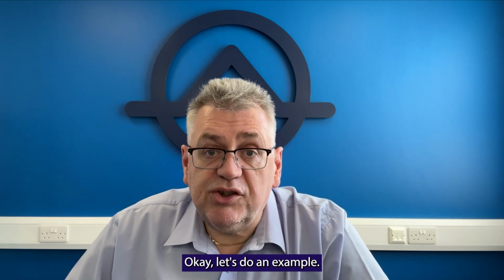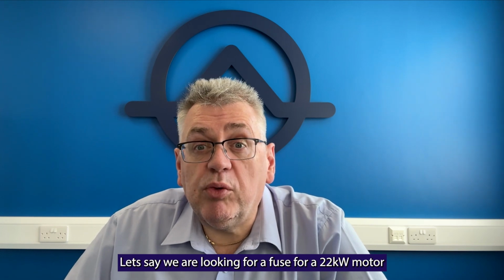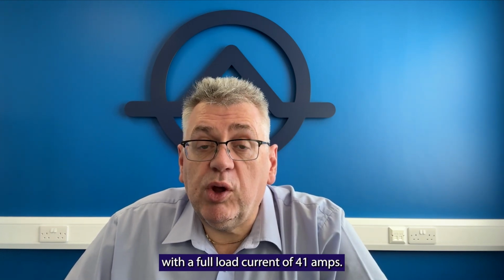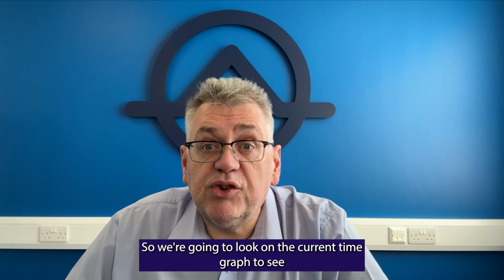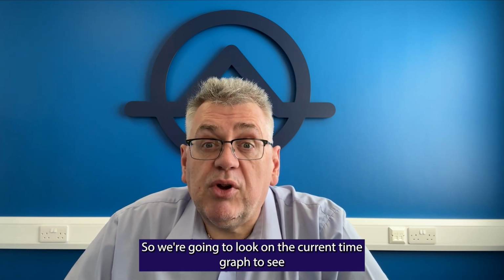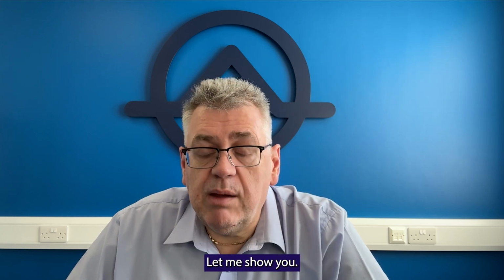Okay, let's do an example. Let's say we're looking for a fuse for a 22 kilowatt motor with a full load current of 41 amps. 7 times 41 amps is 287 amps. So we're going to look on the current time graph to see which fuse rating will withstand this current for 10 seconds. Let me show you.